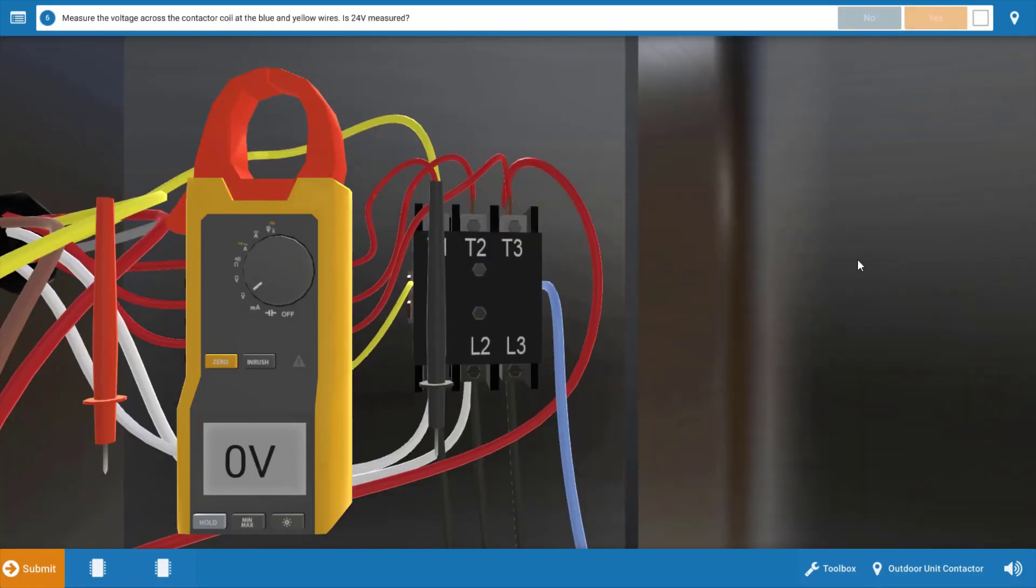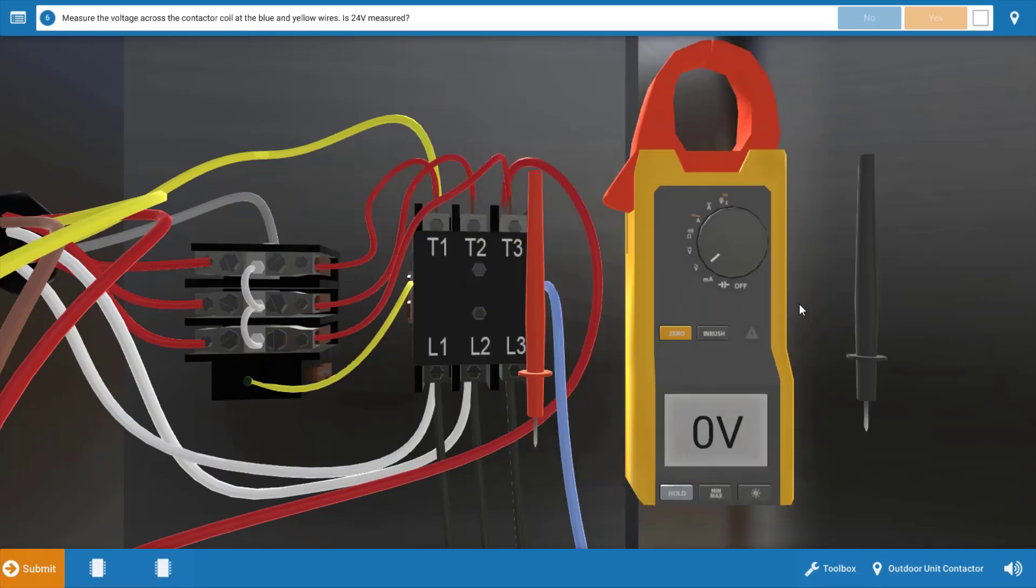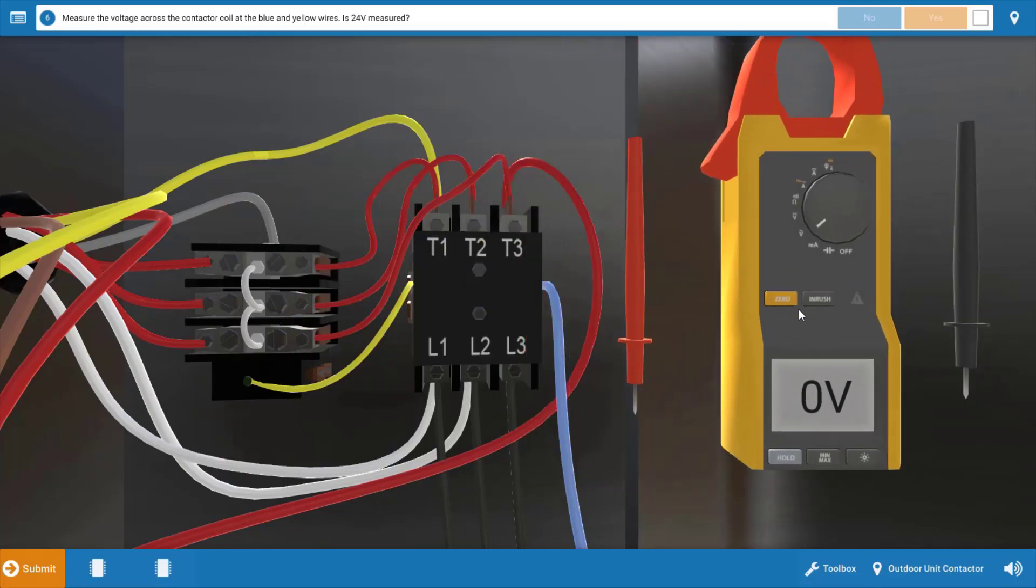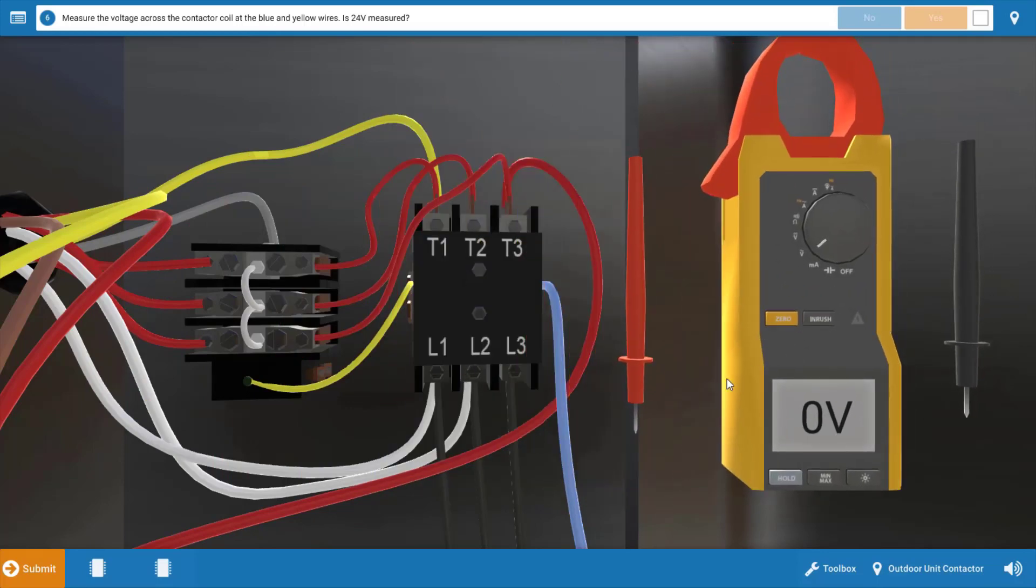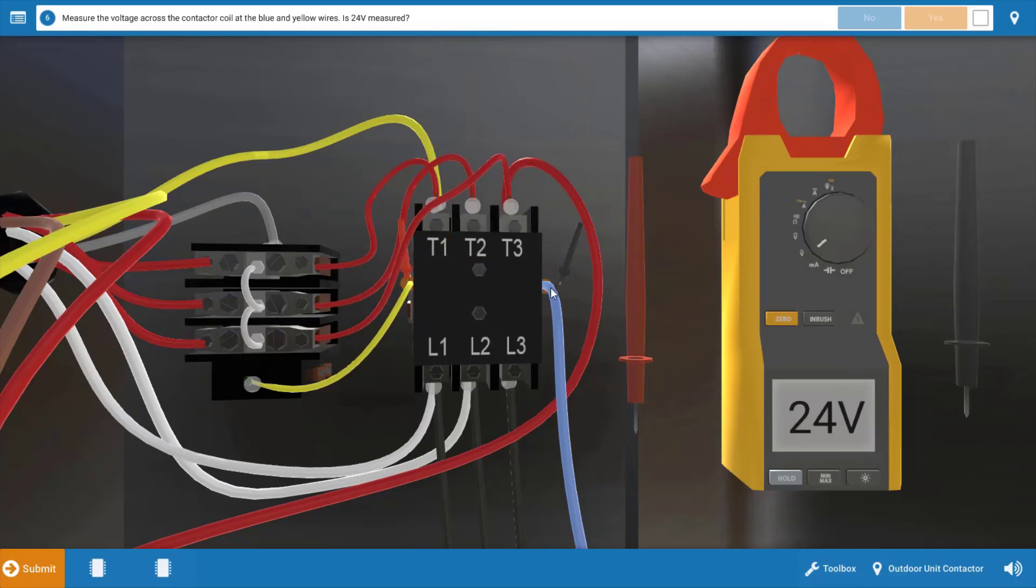So is the compressor cycling? No. Now, our next step now is to find out which of those previous components that we talked about, the contactor coil, the safety switches, as well as the thermostat is at fault here. And probably the easiest place to start is right at the contactor coil. Do we have 24 volts at the contactor coil connections? At the yellow connection here on the left and at the blue connection here on the right. And when we do this, we do in fact have 24 volts to the contactor coil.